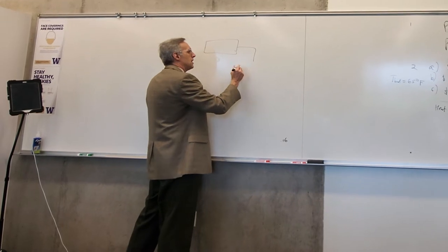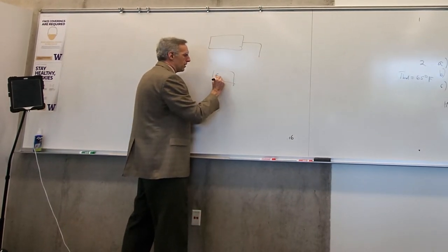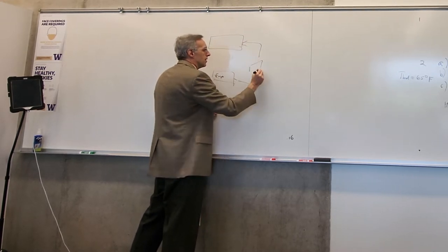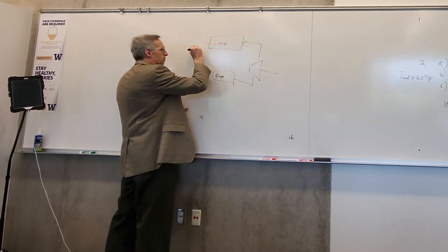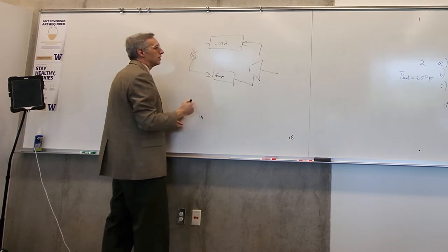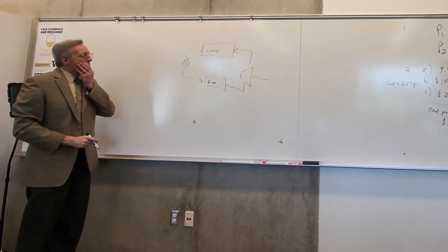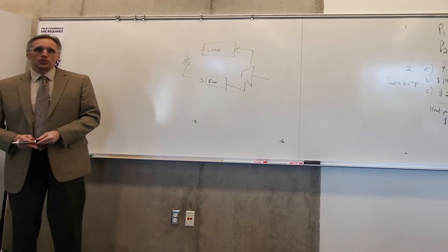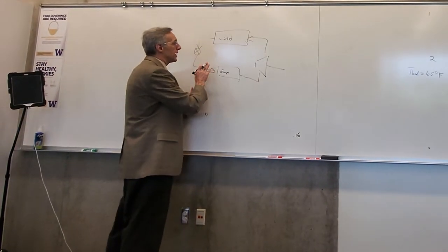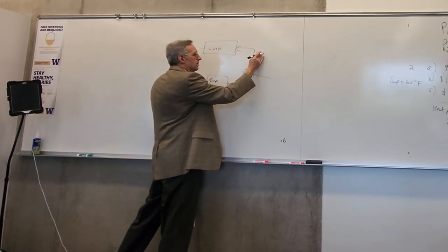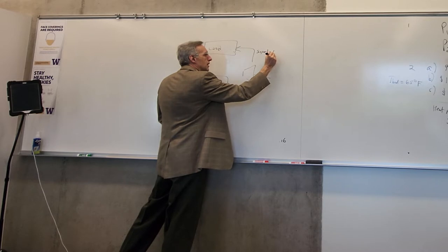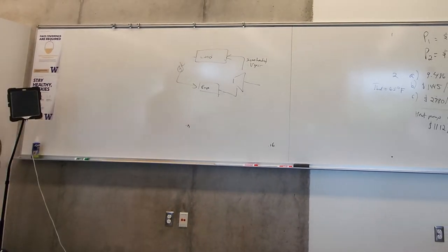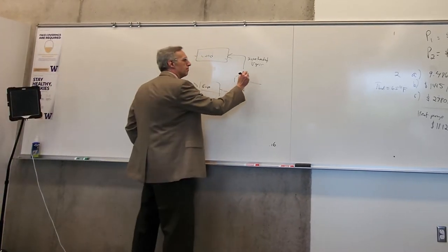And what you typically do with the heat pump is use your evaporator. You've got your compressor here, your condenser. So if you're going to do a hot water heater, and you can do this for a heat pump that's providing heating and air conditioning, it's a really nice way to knock out a bunch of different things with one mechanical system. When you come out of the compressor, you have very hot, superheated vapor at very high pressure, 120 to 140 psi, probably.